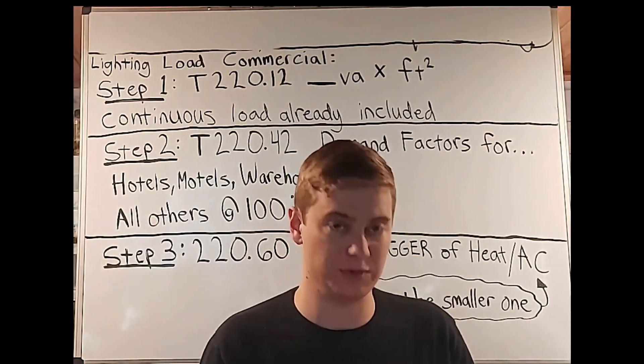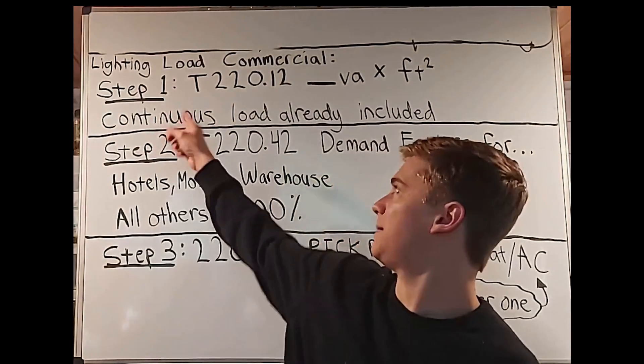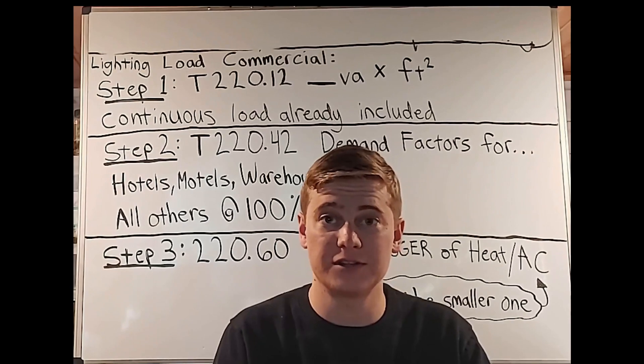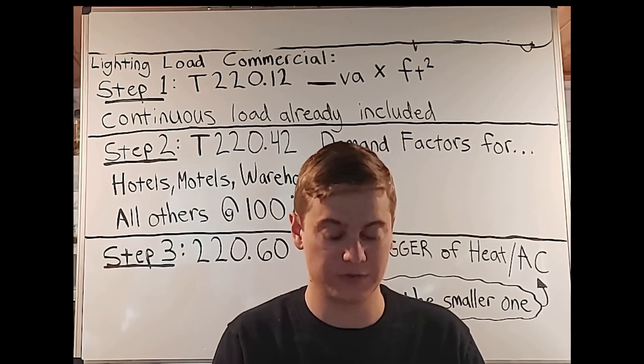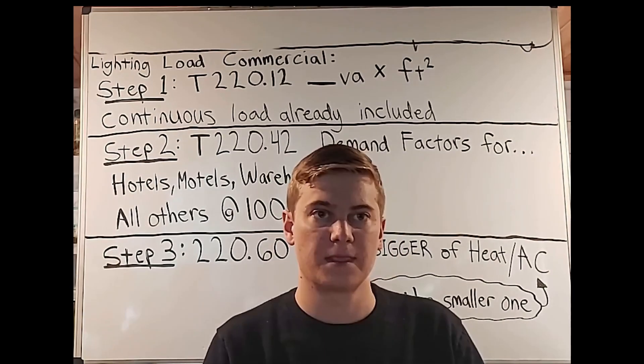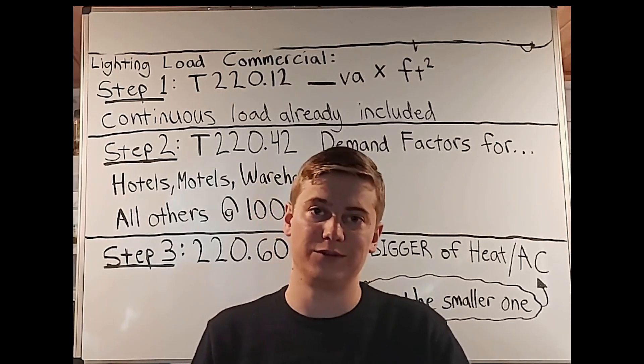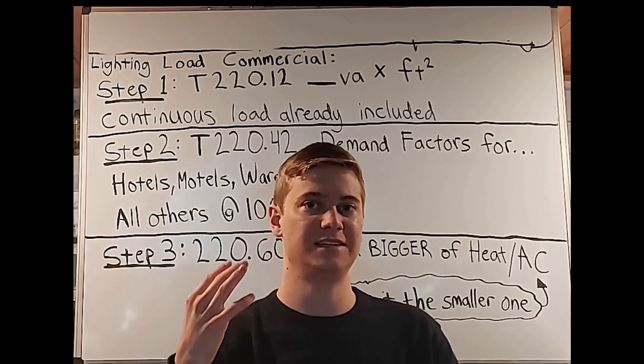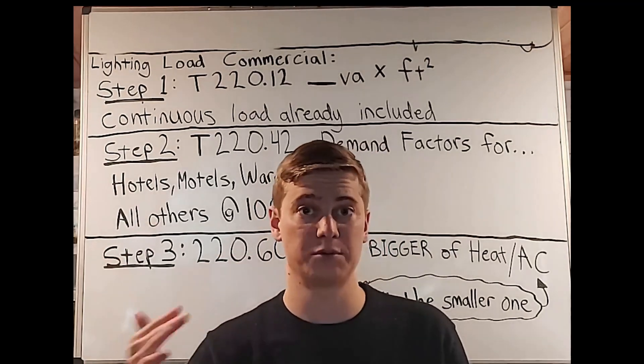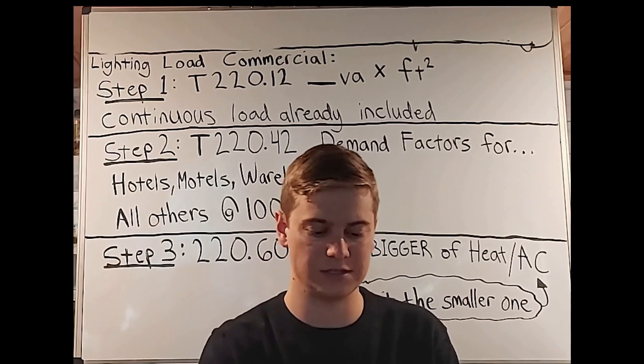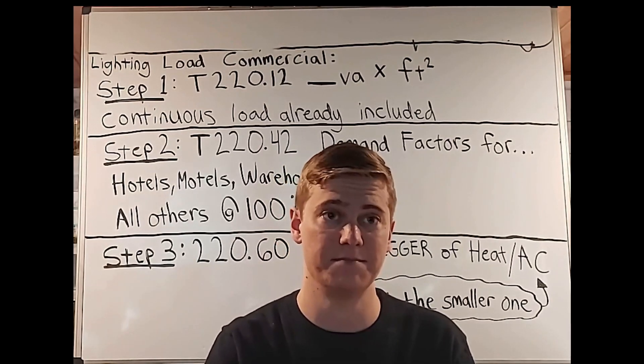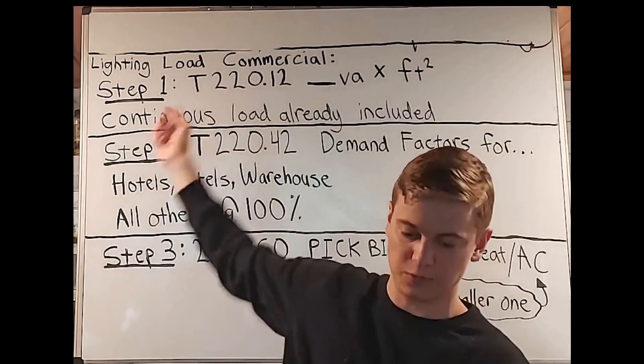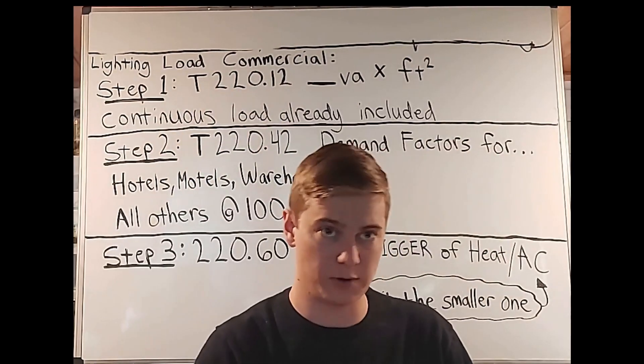This table is what you're going to use for step one of the commercial load calculation. Under the table there's a 125% multiplier for continuous load. When dealing with continuous loads in commercial occupancies, we need that additional 125%. The good news is that using this table already has that math built in — the continuous load is already included in table 220.12 when you're using the volt amperes per square foot.